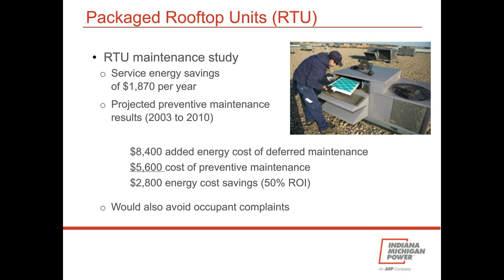IEER efficiency was improved from 7.8 to 9.5. So about a 22% performance improvement, resulting in energy savings of about $1,870 per year. Now, it wasn't returned to the factory rated IEER of 11.2, and you might ask, well, why not?